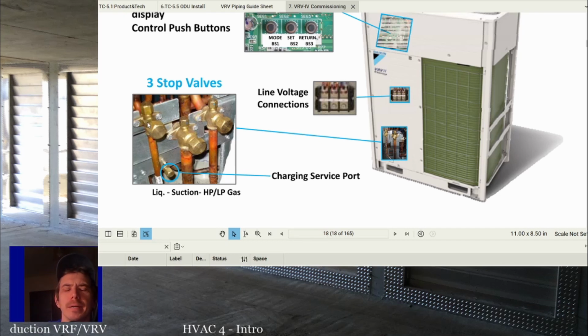And remember, like I said, liquid is your smallest, suction is your biggest, and then high pressure, low pressure is your medium sized line. Try and remember that in case you ever do a VRF system, because you'll get confused sometimes which pipe is which. And you can kind of try and remember based on this. You still have to be very careful when you're piping it to not get these lines mixed up. But that will help you keep them from getting mixed up a lot of the time if you just pay attention. What's my smallest one? What's my biggest one? What's my medium sized one? So those are the three pipes that come out of it.